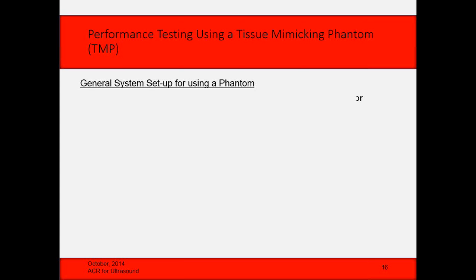So what I always tell people, teach people, is set the system controls for what I call a raw image. So like in the old days when we didn't have all these fancy features on the systems. So turn off SonoCT or compound imaging or spatial compounding, whatever they call it on that system. Turn off all the post-processing smoothing algorithms that they use. Anything you can turn off. Go to one focal point. So try to make the image just as raw and basic as possible.